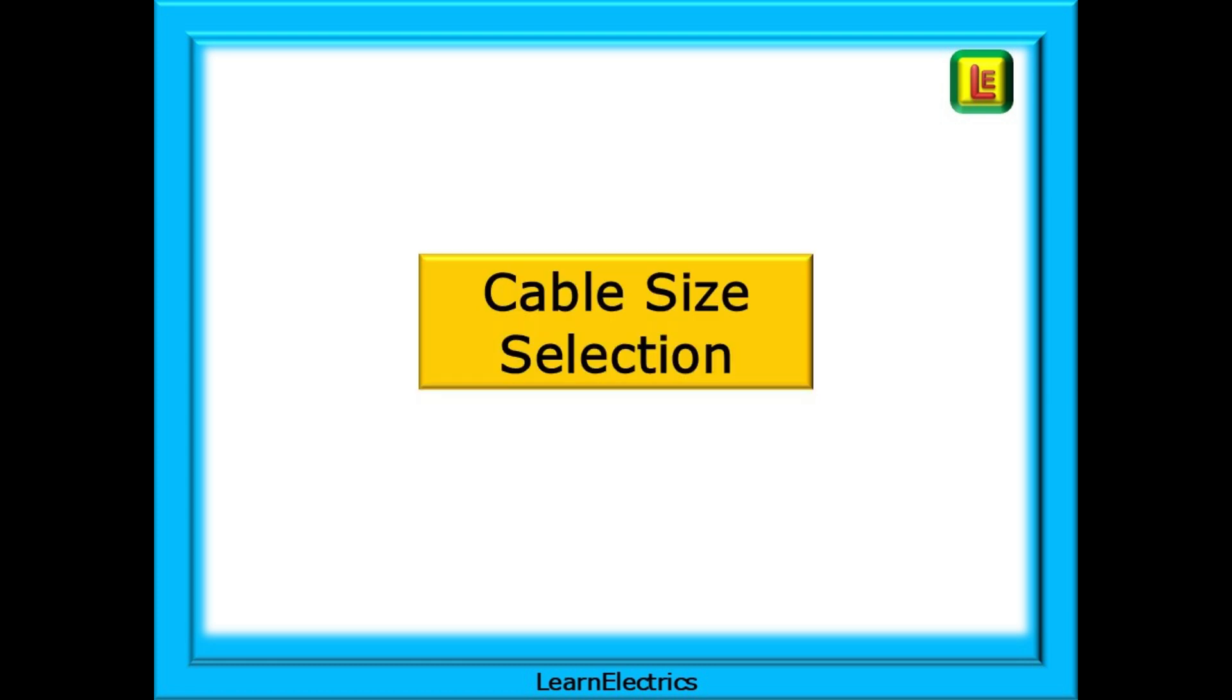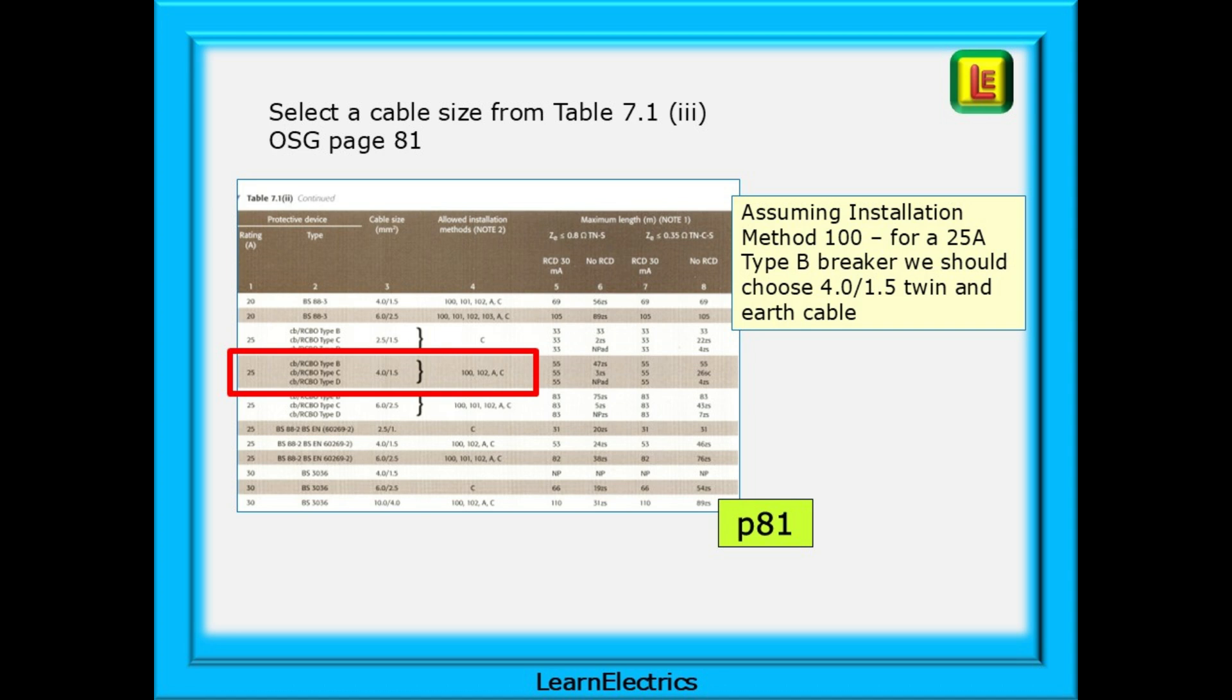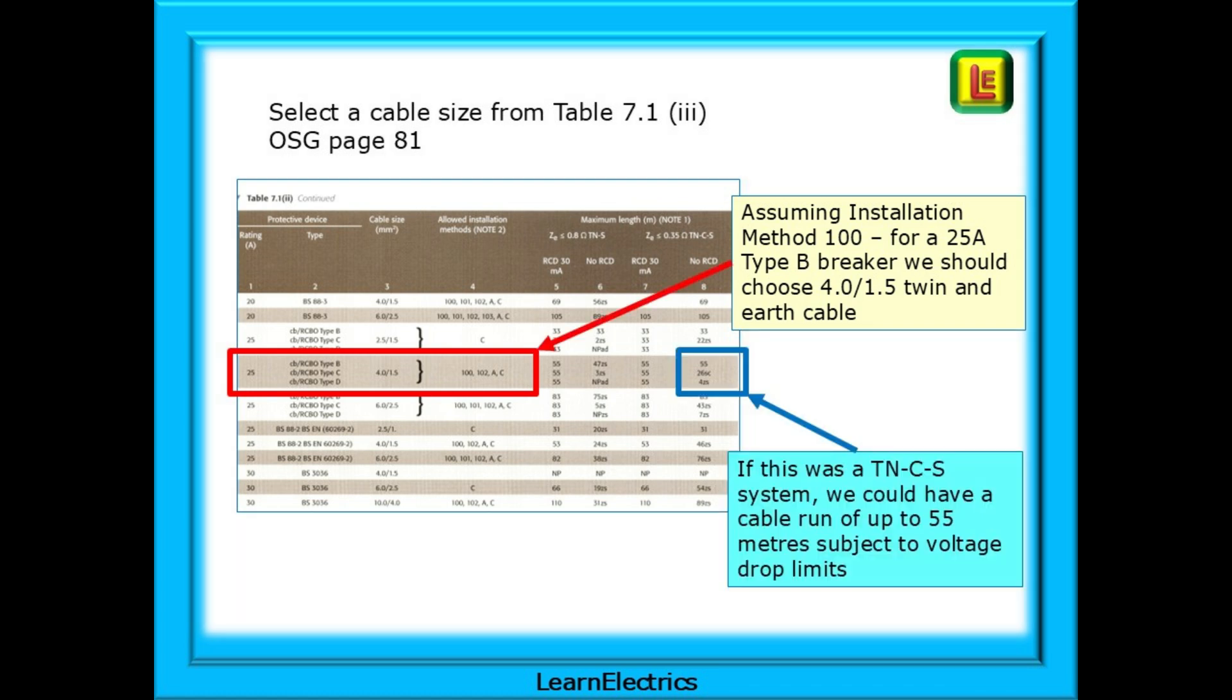Now that we've selected a breaker, we can move on to cable size selection. Table 7.1.3 in the on-site guide covers several pages. Take some time to study the layout and order of these pages. We want page 81. We will make some assumptions and assume that the installation method 100 applies. And the table shows us that, for a 25 amp type B breaker, we should choose 4mm by 1.5mm twin and earth cable, as shown in the red box. The table also tells us that, if this was a TNCS system, then we could have a cable run of up to 55 metres subject to voltage drop limits. And we should check this next.